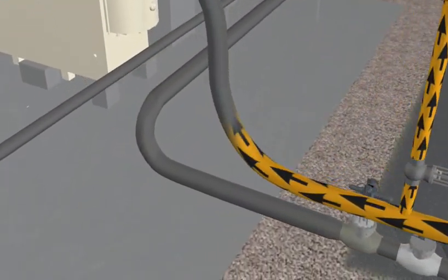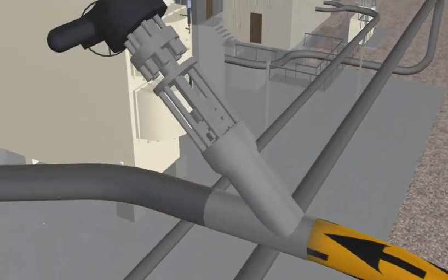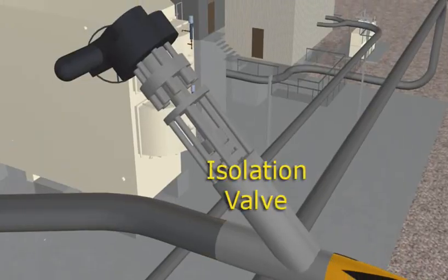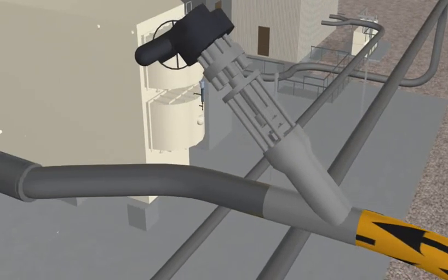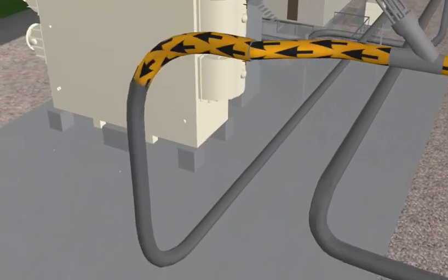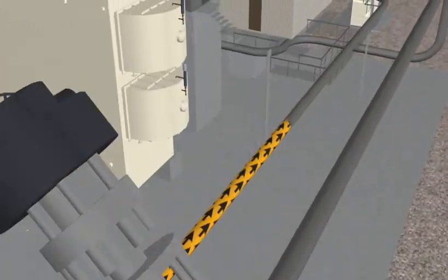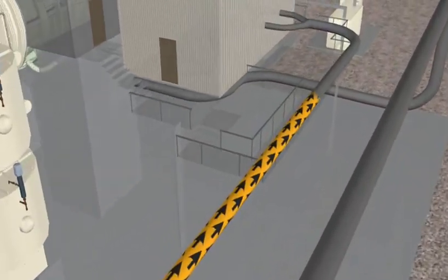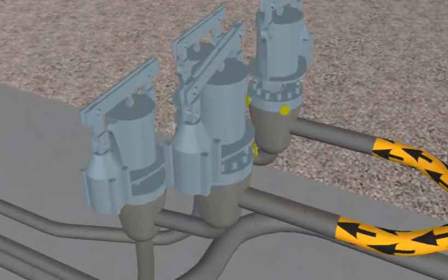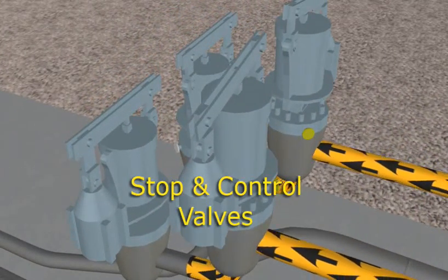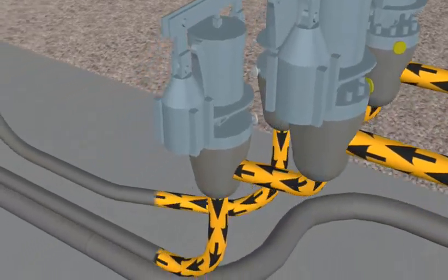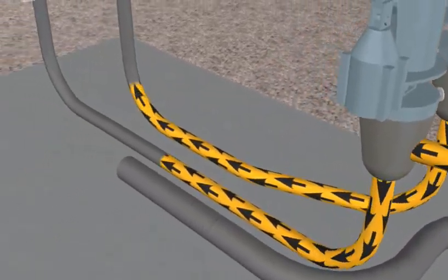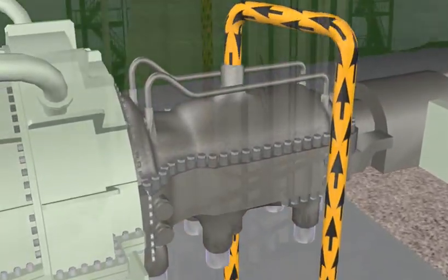From the bypass valves, main steam continues on to its isolation valves. From the isolation valves, the steam goes to the steam turbine enclosure where it has two sets of stop and control valves. There's one set of valves for each main steam line that passes to the main steam section of the turbine.